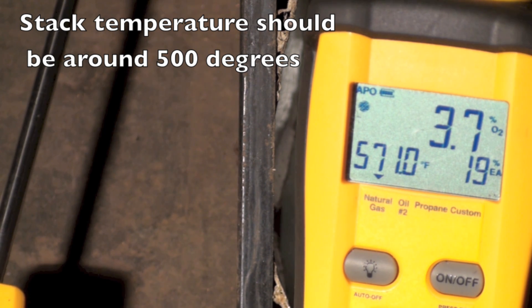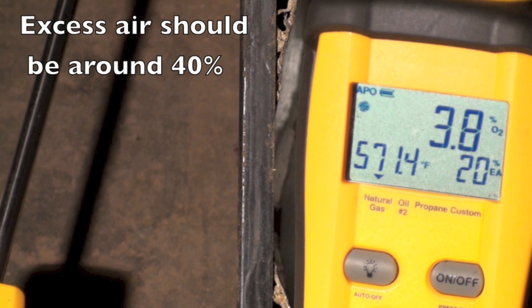Excess air is 19%. Now excess air is more air than is needed for combustion in an ideal sense. The excess air is showing around 20% now.